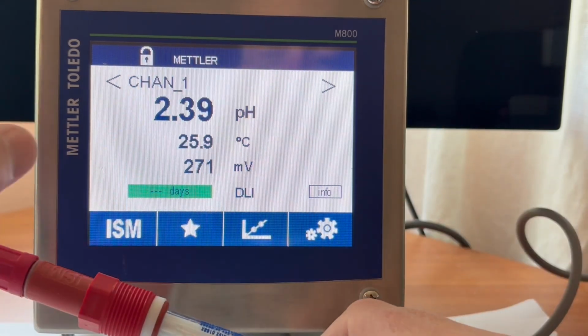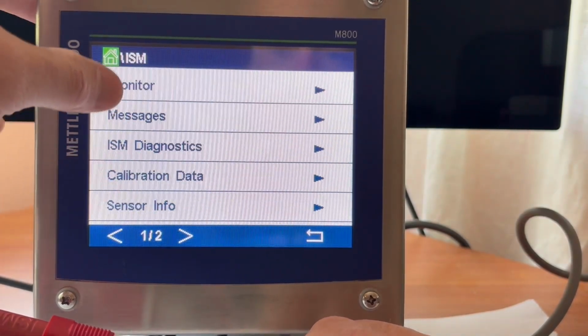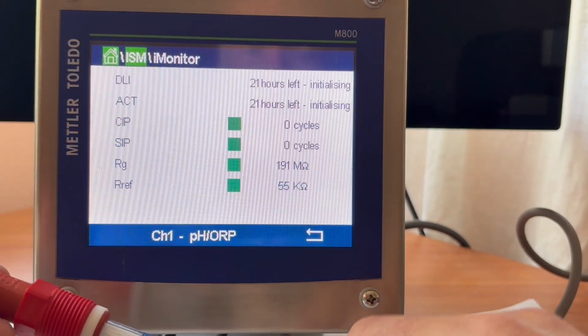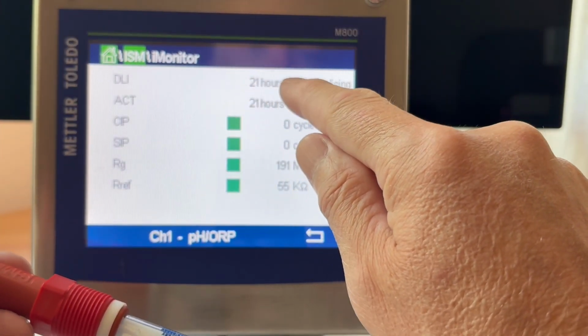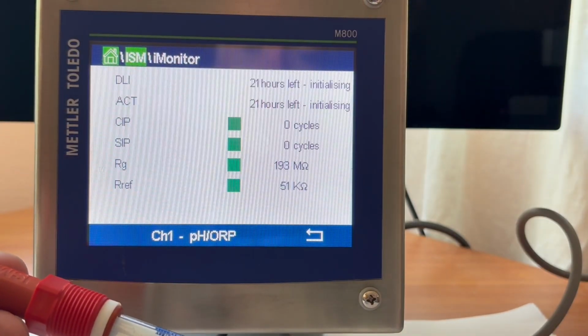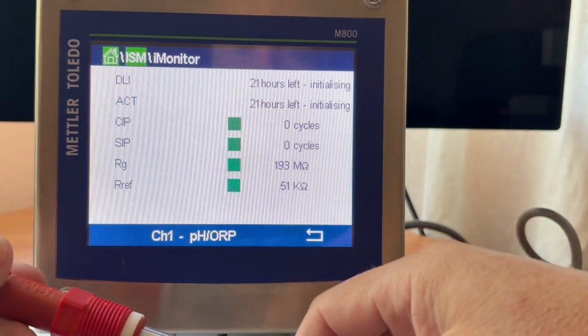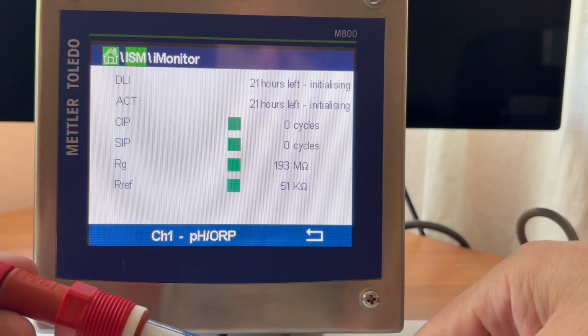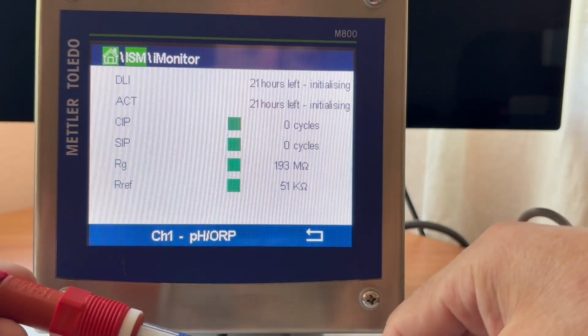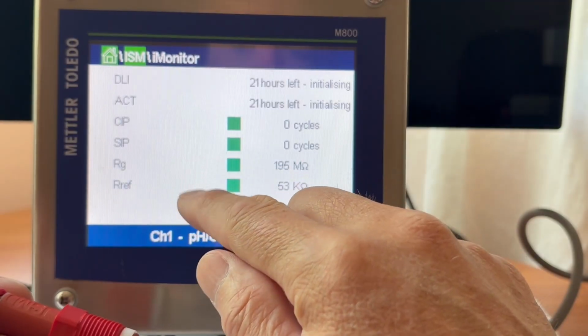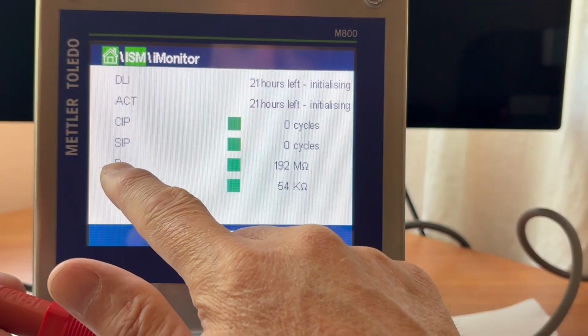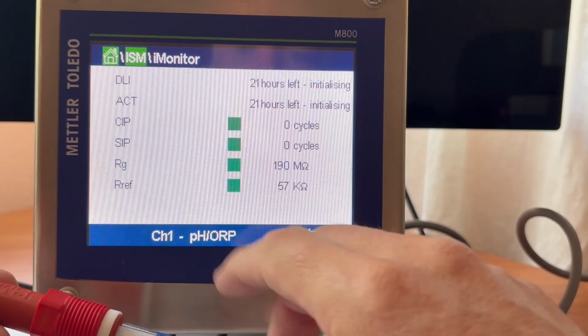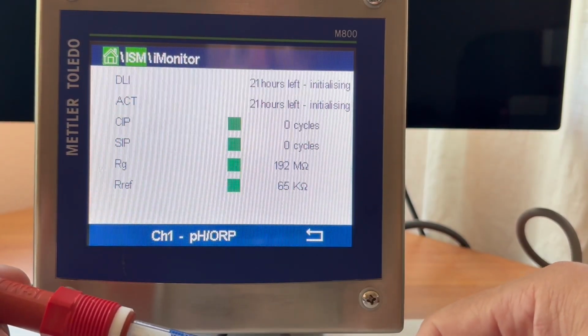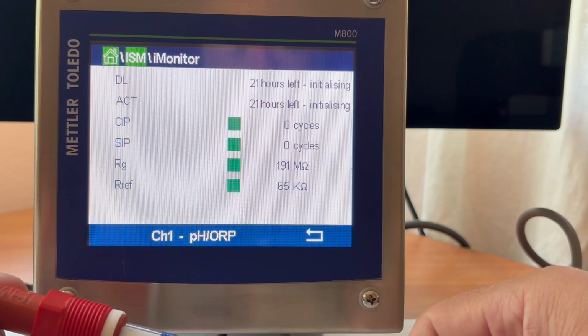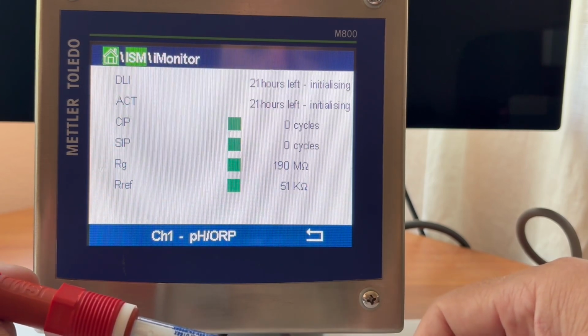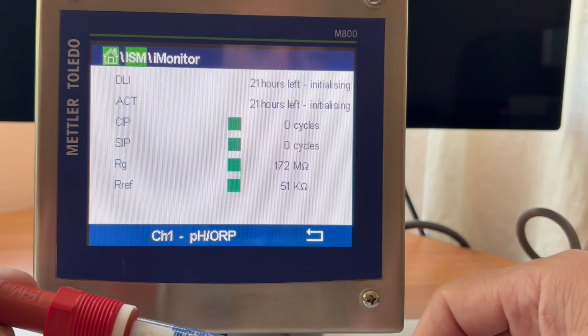If I want to look at a bit more information, I go into two steps, ISM, iMonitor. Again, here it's telling me you've got to wait 21 hours before your DLI is going to show as a value, and it's also going to determine how much longer it would need before it needs to be calibrated. Those are both being calculated as we speak. Important information is impedance values on the glass, which is the RG, and impedance on the reference. These would be pertinent to sensors that get fouled in the process, coating, and therefore need to be cleaned. Clean then improves my calibration.